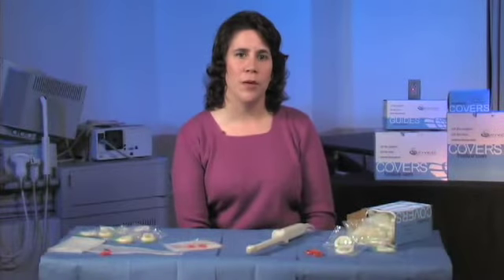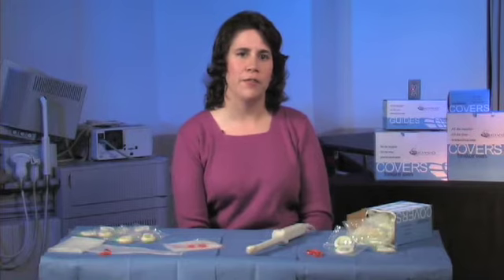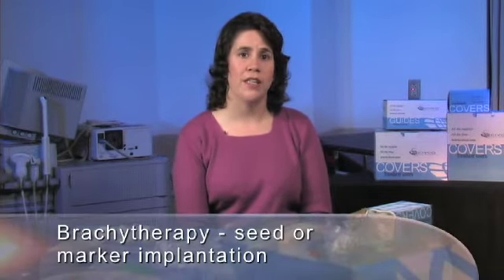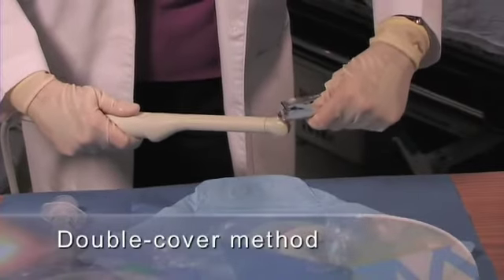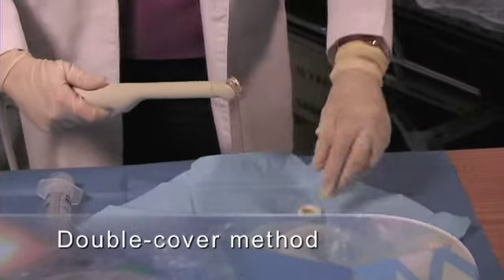When performing a transrectal ultrasound, there are several types of transducer covers available. Transrectal ultrasound is an invasive procedure that may involve tissue biopsy or brachytherapy, seed marker implantation. Some transducers use a double cover method to create a balloon or water bath through which to scan.